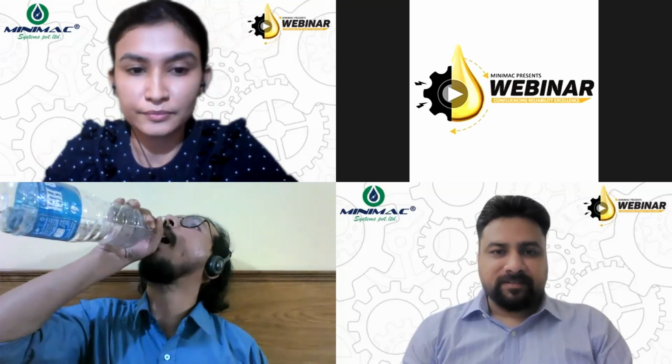In both these cases, you need to adopt a micron filtration system or mechanical filtration system for the maintenance of your compressor. Why I talk about mechanical filtration systems is because your compressor oil might have certain additives which are not compatible to the electrostatic type of purification activity. So if you want to achieve NAS levels and ISO 4406 levels, the best way and the safest way to do it would be mechanical filtration systems.